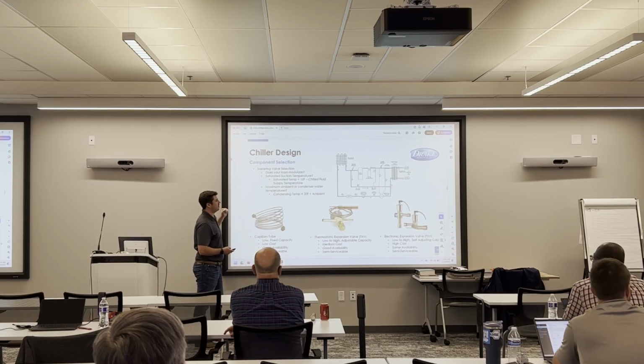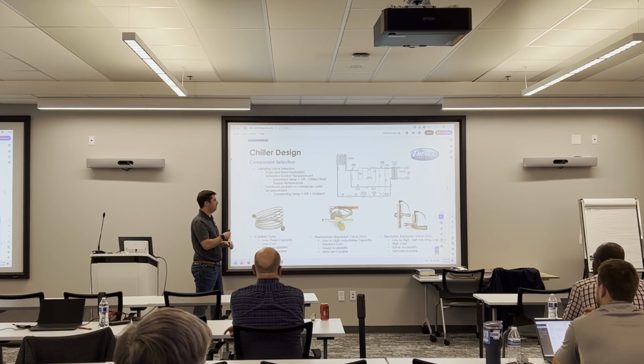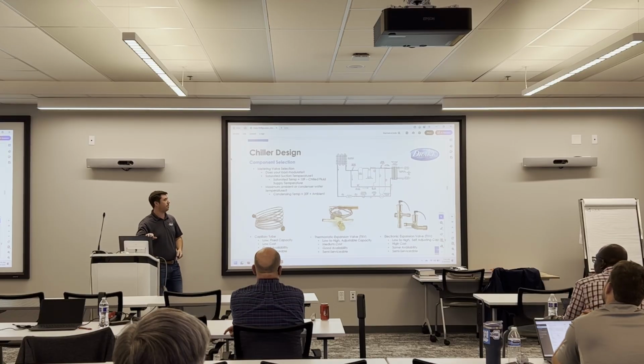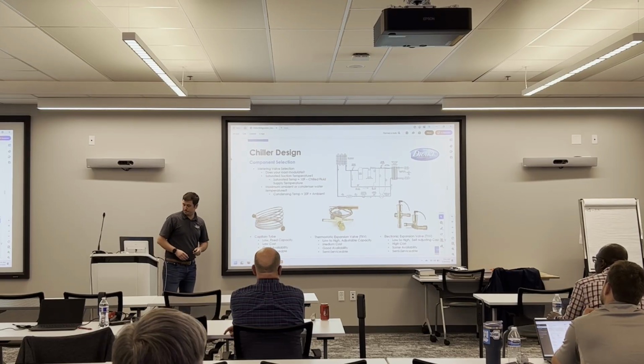If the refrigerant starts moving too fast, then our superheat decreases, that valve will self-correct itself, close itself off, increase your superheat, and vice versa. Like if you're not throttling enough refrigerant through and your superheat's too high, it'll open itself back up again. So again, some availability, semi-serviceable.